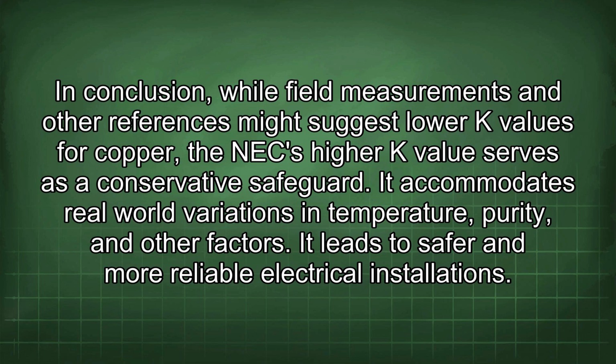In conclusion, while field measurements and other references might suggest lower K values for copper, the NEC higher K value serves as a conservative safeguard. It accommodates real-world variations in temperature, purity, and other factors. It leads to safer and more reliable electrical installations.